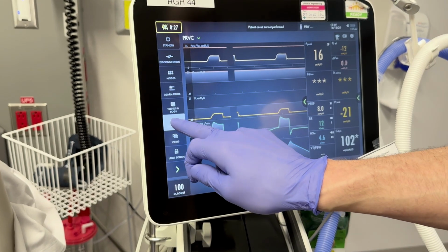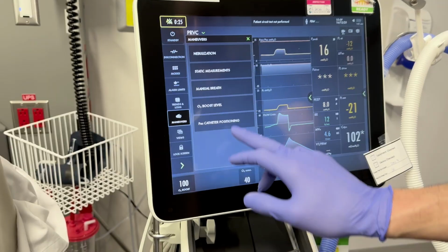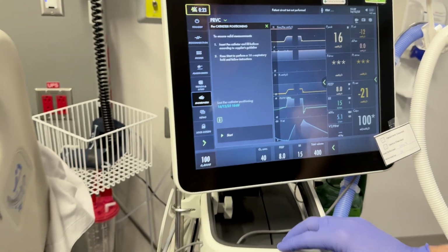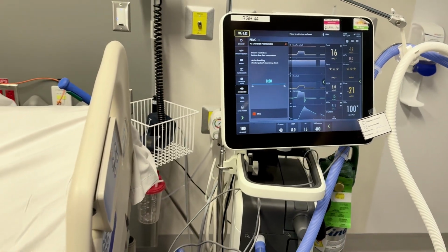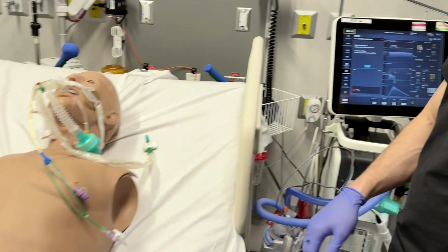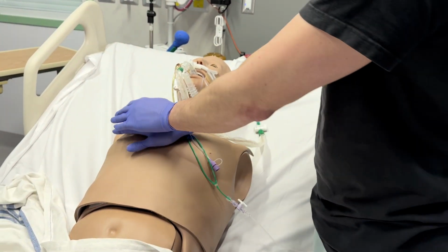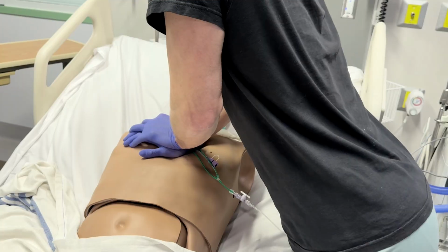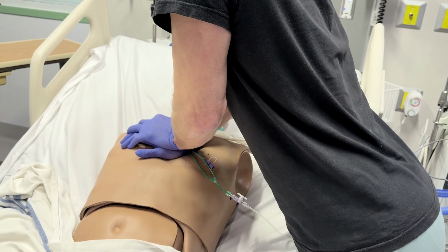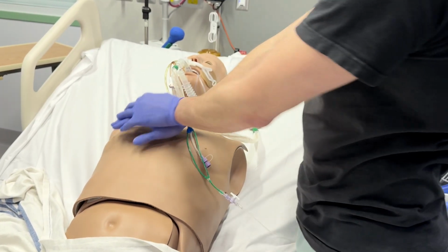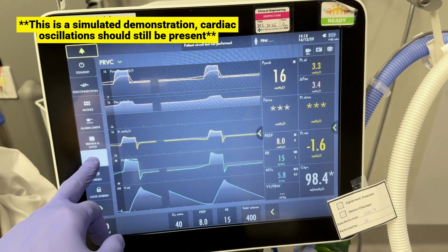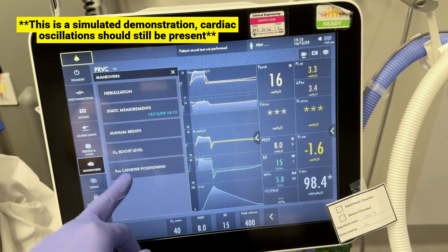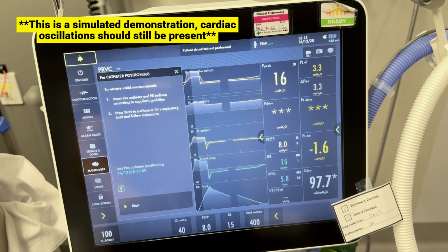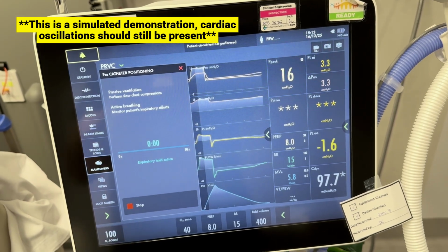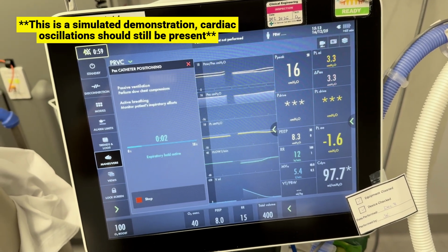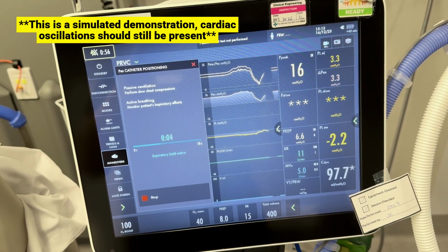To perform the occlusion test on the ventilator, select Maneuvers, then Pes Catheter Positioning. When ready, select Start and wait for the beep to sound. Then perform 1 to 2 slow but firm compressions on the mid to left side of chest within 10 seconds. You should observe a positive deflection on the ventilator waveform. If the maneuver was successful, the ventilator will display a green light. Acceptable ratio is 0.8 to 1.2.